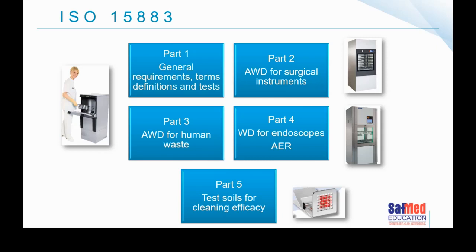Part three of ISO 15883 refers to a device used to clean human waste — a bedpan washer or urinal washer. Part four is the washer disinfector used for endoscopes — automated endoscopic reprocessors. Part five goes into detail around the test soils. We need to test these machines to make sure they're doing the job they're intended to do. We can't inoculate instruments with proper contaminants all the time in a laboratory setting, so there are a variety of test soils — Edinburgh test soils, various European recipes, and some commercially available options.